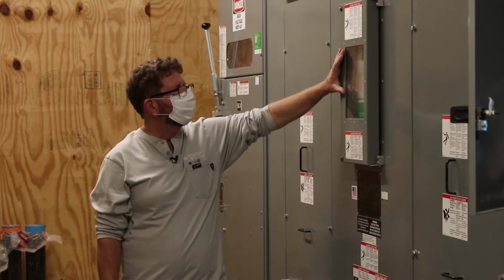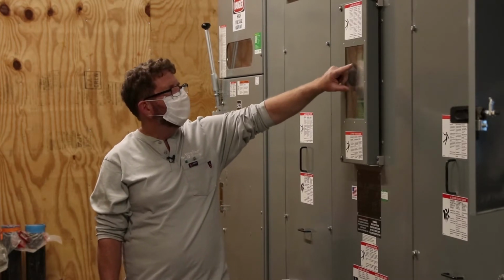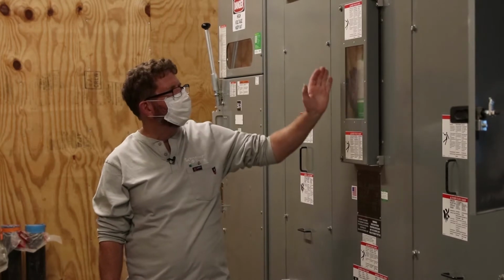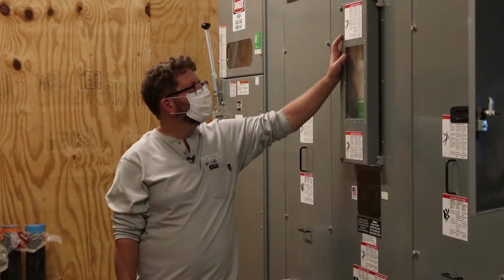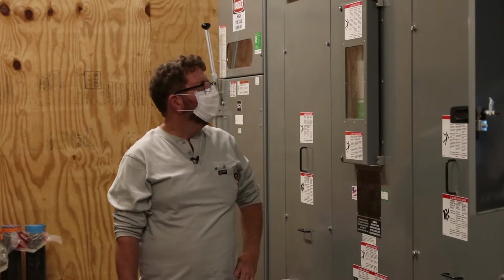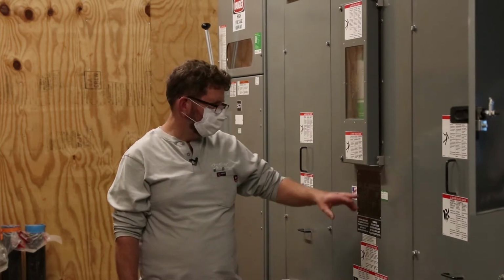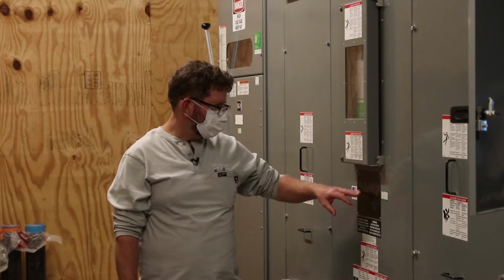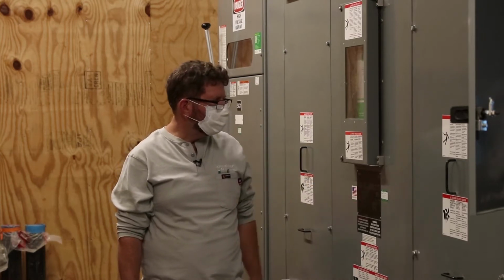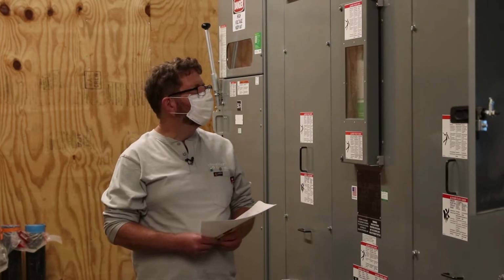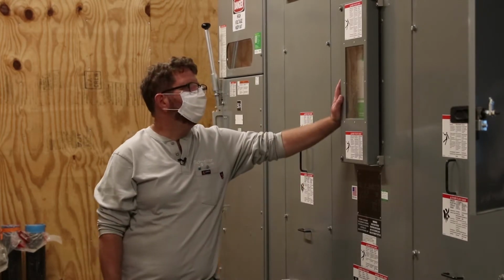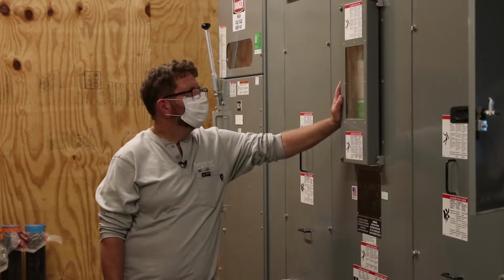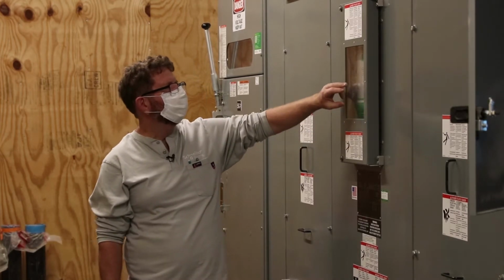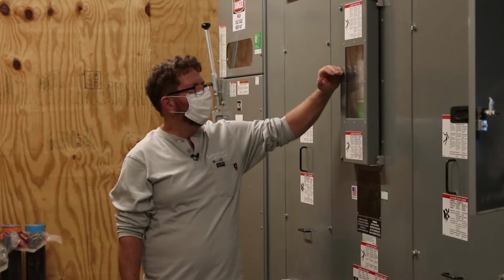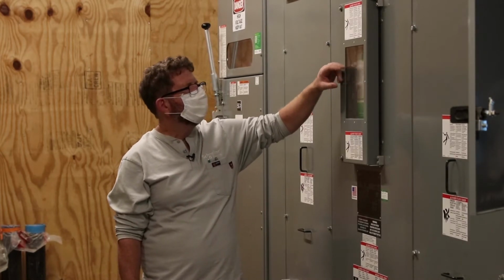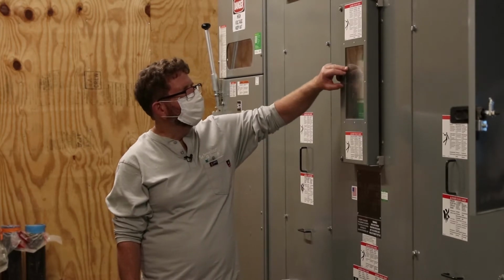The fan controller, Model 98 temperature controller, like I said, it monitors and starts the fans that also give alarm. It's going to continuously scroll through the 3 coils and tell you what those temperatures are. This is a 150 degree C transformer at, can't remember what the set point is, we can look it up later, but at some set point it's going to cycle the fans on.